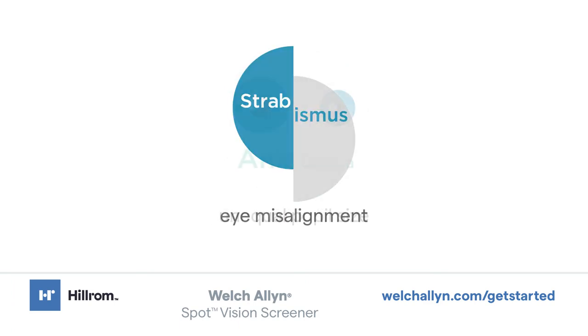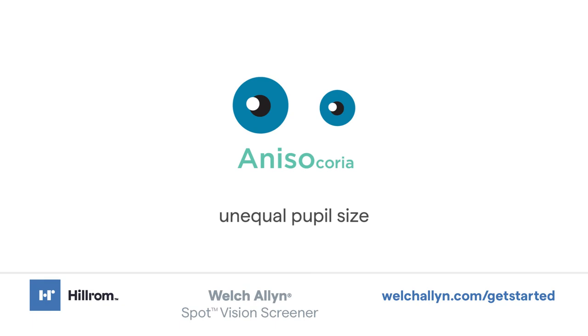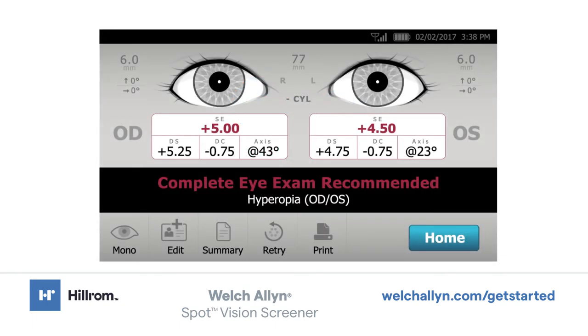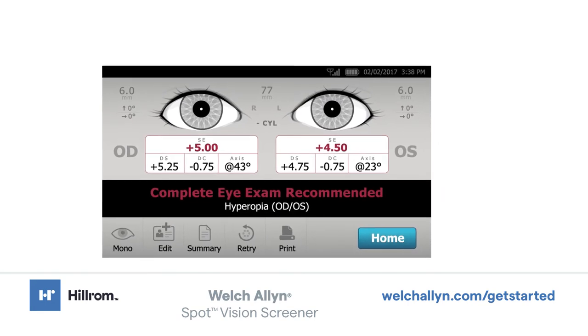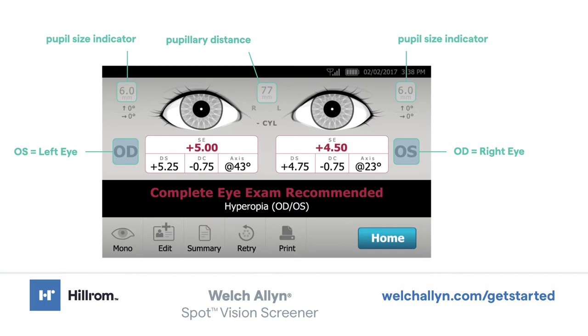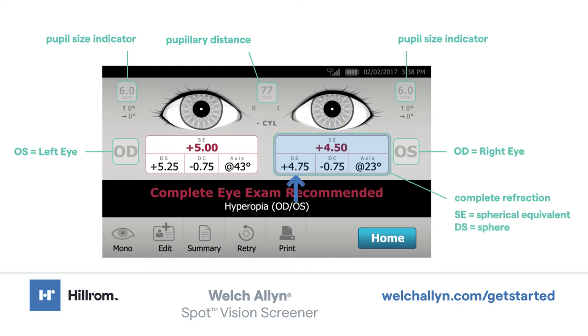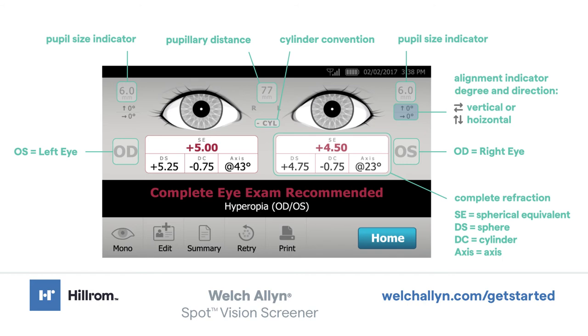Additional risk factors include strabismus (eye misalignment) and anisocoria (unequal pupil size). The Spot Vision Screener provides instant on-screen data and a printed summary report to explain the conditions detected. On-screen measurements include pupillary distance, pupil size indicator, right eye, left eye, complete refraction, spherical equivalent, sphere, cylinder, axis, cylinder convention, alignment indicator, degree, horizontal, and vertical.